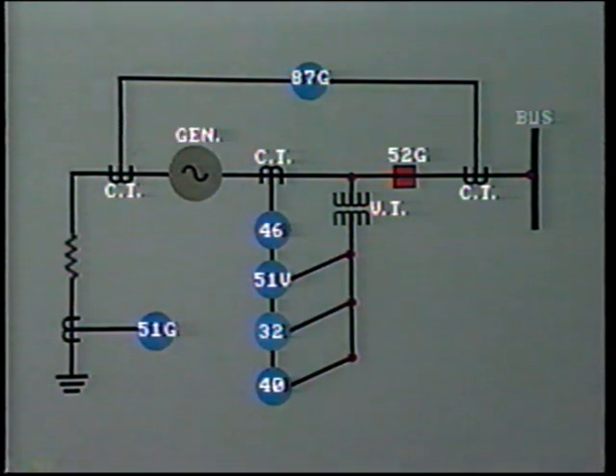A generator connected directly to a bus through circuit breaker 52G. You can already recognize some of these device numbers. 51G is a time over current relay in the neutral to ground. 87G, a differential relay across the generator. What is this 46? A negative phase sequence relay. 51V is a voltage-restrained time over current relay fed by the CT in the generator output, and a voltage transformer which also feeds a directional power relay, 32, and a loss of field relay, 40.